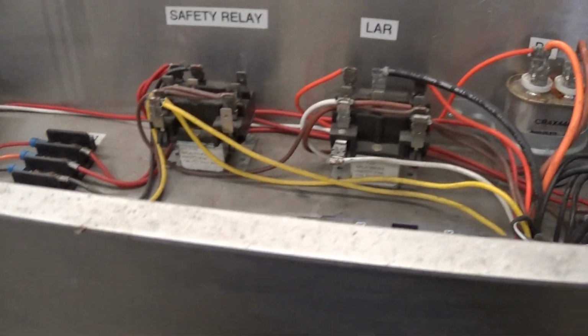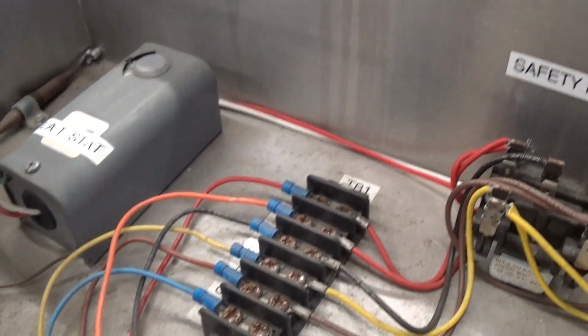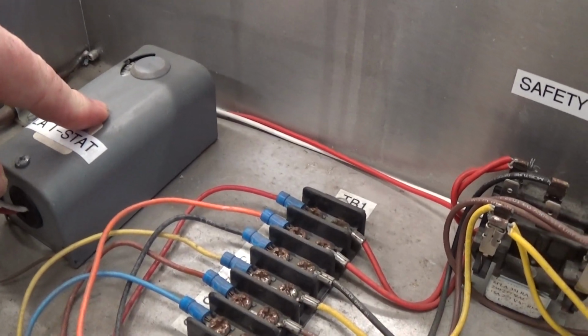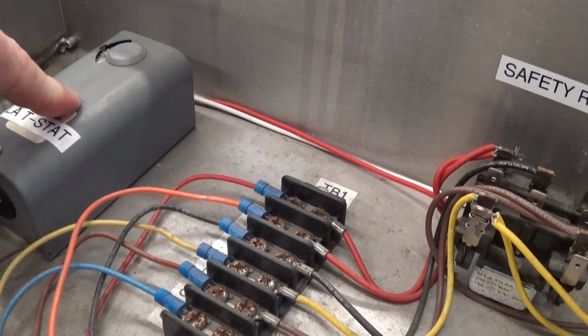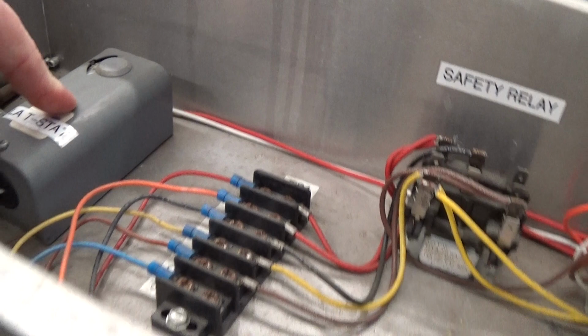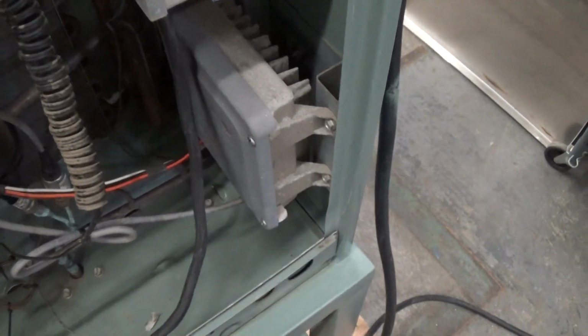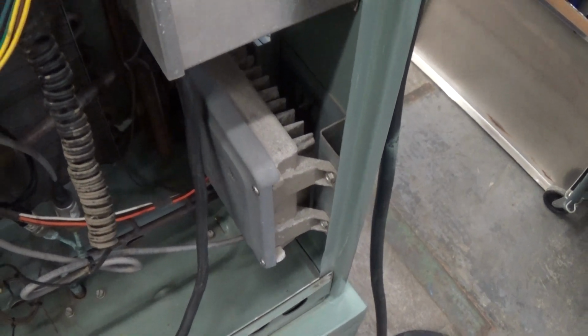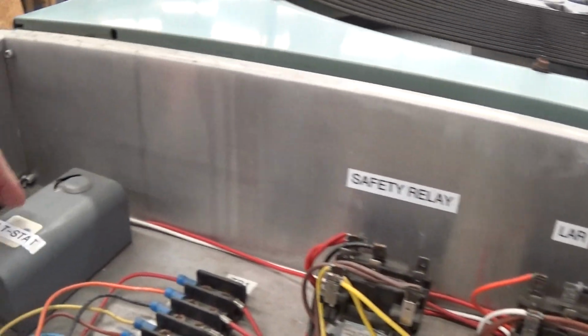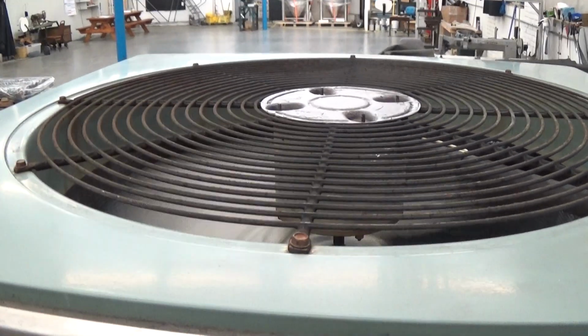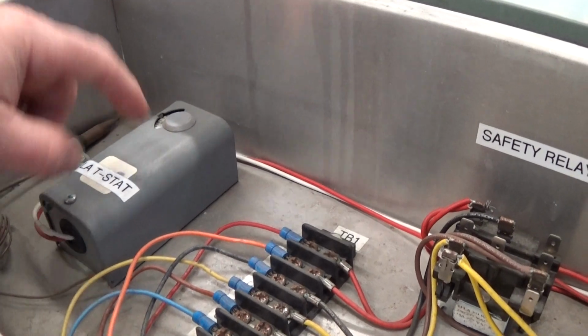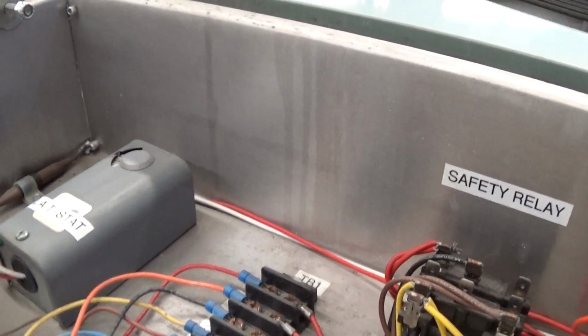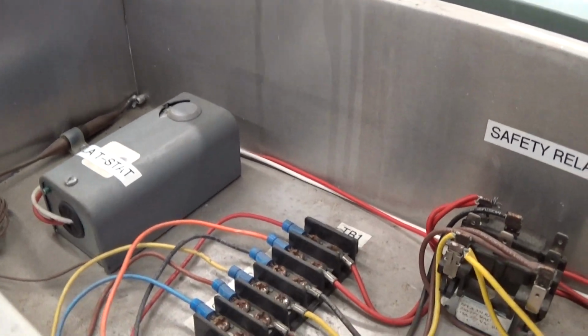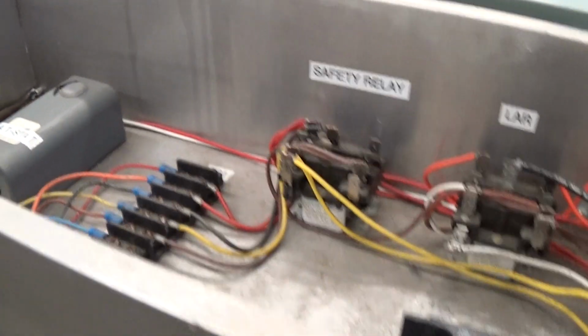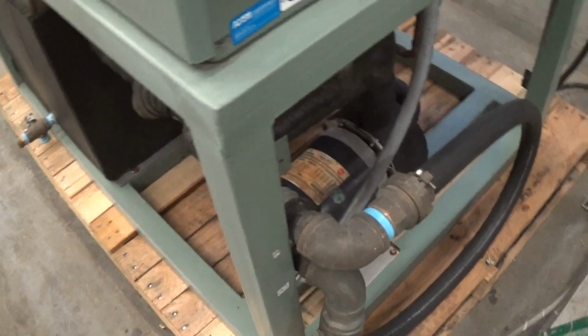So right now in the shop here, we have the low ambient thermostat. It's going to be set at about 70 degrees. So that means anything below 70, the low ambient control or fan speed control is going to be run by the P66 fan speed controller. Above 70, it will click and the fan will run full speed. Depending on your ambient conditions, we may end up adjusting this, and we'll help you over the phone. But this is an outdoor rated unit with that low ambient feature. You can hear it running right now. We have a 2 horsepower pump here, insulated.